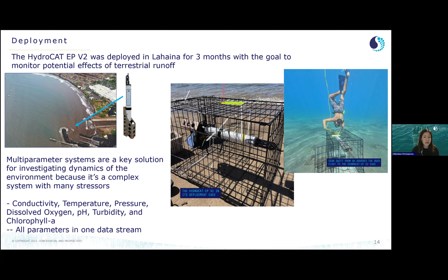So in biologically rich environments, as the Lahaina coastal environment is, it is typical for biofouling to occur, especially during the first weeks and if the deployment lasts more than a few days, of course. For example, here in this image, you can see we are 1.5 months within the deployment, where significant growth all over the cage has occurred, and in the instrument. The HydroCAT-EP V2 has different anti-fouling measures, ensuring stability of all the measurements. Here on the right side, you can see the optical sensor, turbidity and chlorophyll, remaining clear due to the integrated copper faceplate and the wiper that cleans the sensing window at every sampling interval.